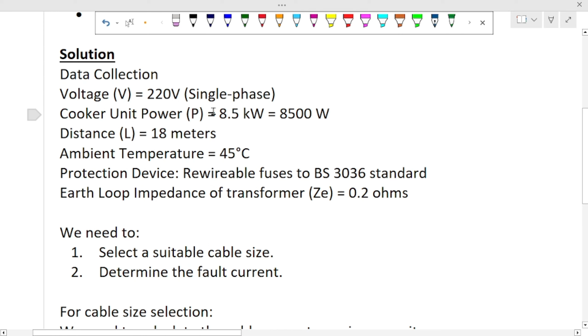Then for IB, which is the total current we are expecting to have in this circuit, that's the design current. For that, we can use the formula P equals IV, making I the subject, which gives P over V. Power in this equation is given as 8.5 kW, 8,500, and voltage is 220. So this will be 8,500 over 220. That will give us IB as 38.6364 amperes.